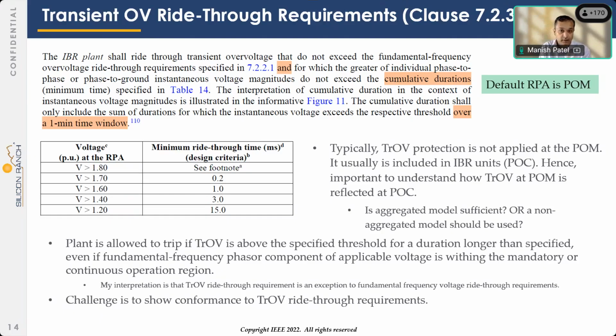So let's pause right there. It says the plant is required to ride through transients that do not exceed the fundamental frequency overvoltage ride-through requirements. If you read this again and again, I think I heard this from someone else, and then it started to make sense. My interpretation is that the transient voltage ride-through requirement is an exception to the fundamental frequency voltage ride-through requirement. For example, fundamental frequency voltage ride-through, right? It uses, in simple words, RMS voltage.